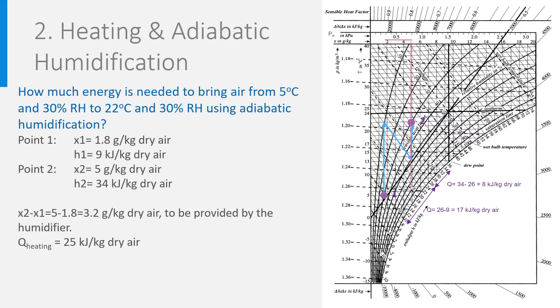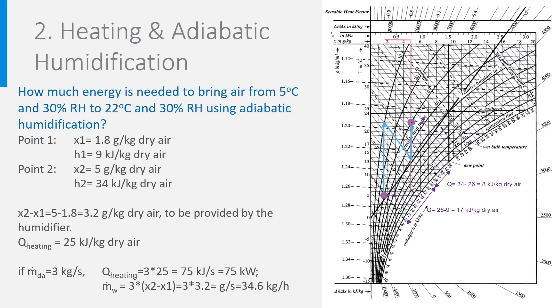With 3 kilogram per second flowing, this leads to a heating capacity of 75 kW and a mass flow rate of 34.6 kilogram per hour. An alternative approach is to heat the air first much more — up to the intersection of the wet bulb line from point 2 and the absolute humidity of x1, corresponding to about 29.5 degrees Celsius — and then humidify down to point 2. The advantage is that only one heater is needed, and the total energy used is unchanged.